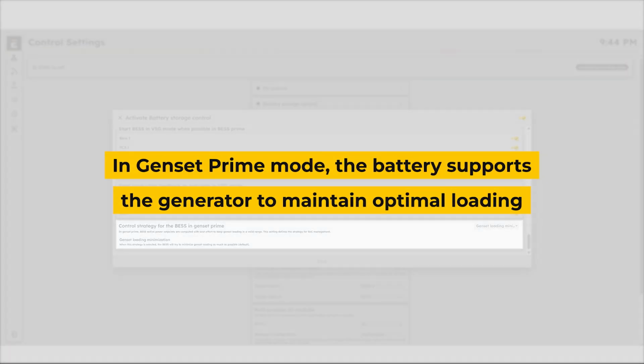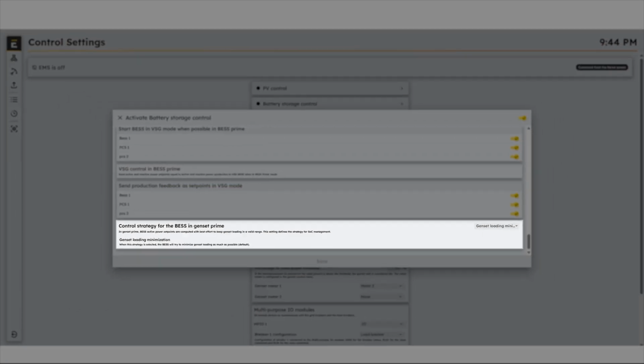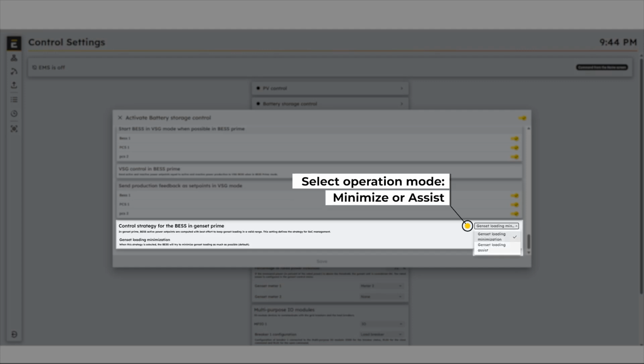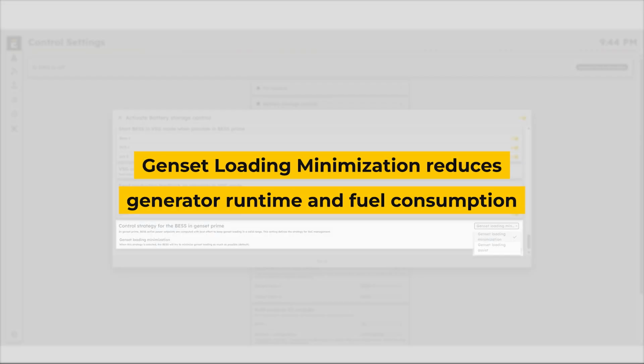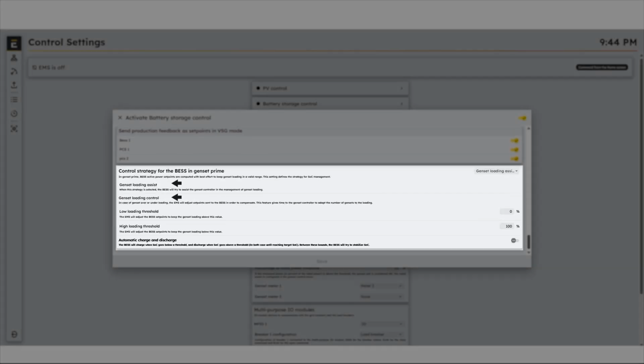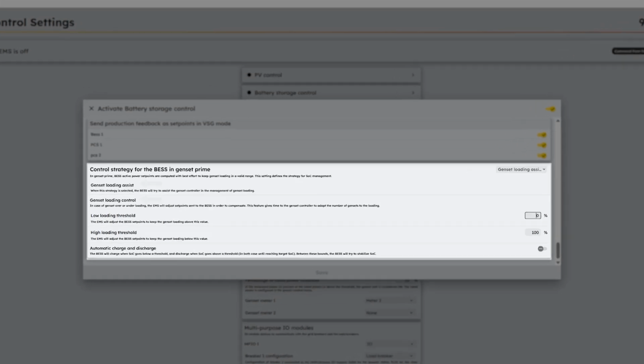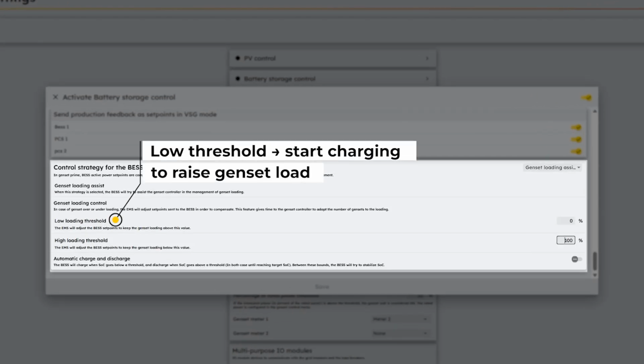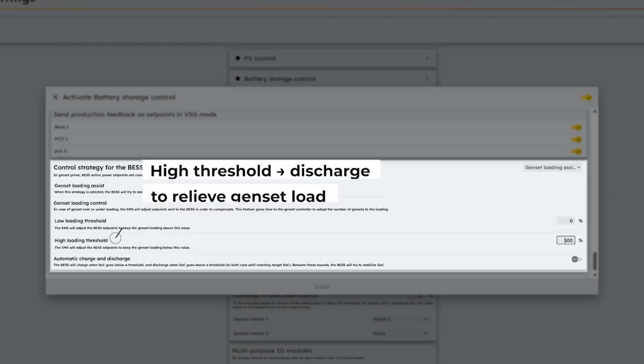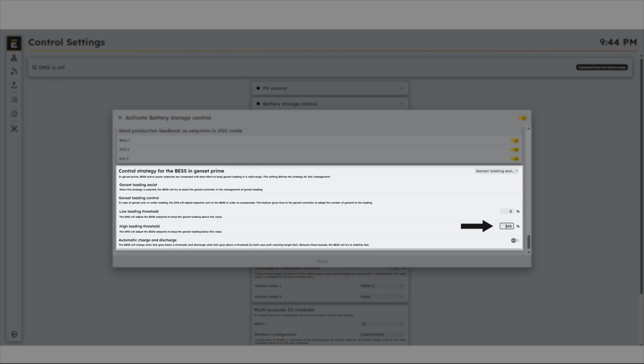When operating in genset prime mode, the EMS defines how the battery interacts with the generator to maintain an optimal loading range. Two main strategies are available: genset loading minimization, which aims to reduce generator runtime and fuel consumption; genset loading assist, which helps stabilize the genset's output by absorbing or supplying power as needed. The low loading threshold sets the minimum the genset should not fall below. Below this value, the BESS begins to charge to raise the load. The high loading threshold marks the upper limit. Above this value, the BESS discharges to lighten the generator's load.